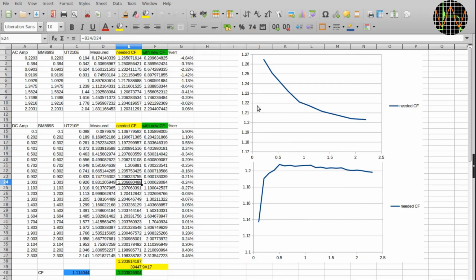We could use the AC or DC measurements for finding the best compromise correction factor, but I favor the DC measurements because the AC values are fewer and they have the inherent problem that the mains voltage, and thus the transformer voltage and therefore the current, is always varying. So it's problematic to compare readings from two instruments. You read one and when moving your attention to the second one for comparison, the mains value may have changed already. On the DC values, I discount the very beginning, where measurement errors are always proportionally largest, and came to an average correction factor of 1.2038 in yellow, which converts to a rounded new cal value of 39,447.